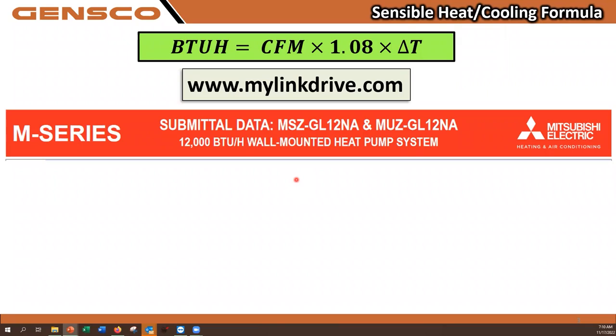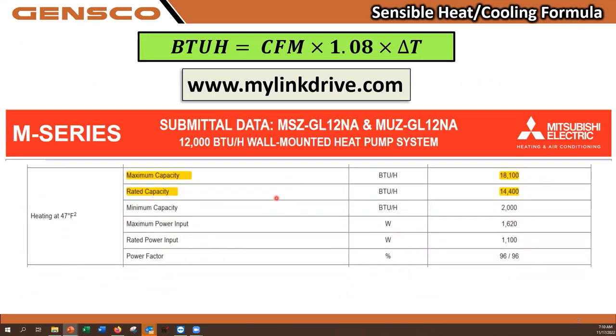So again, we're going to use the MSZ-GL12 with an MUZ-GL12 outdoor unit. When I go to the submittal, here's my capacities. The rated capacity is the one I'm concerned about. This is the one that's the legal document. This is what the unit should produce. And if you installed it correctly, this is what we guarantee you to get.